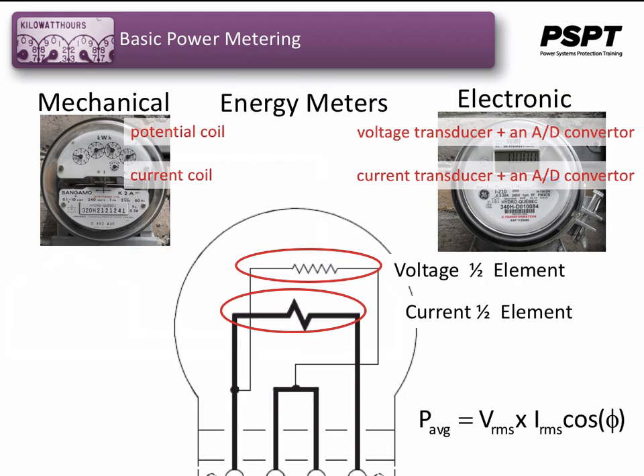Remember from a previous chapter that energy meters, regardless of their makeup, mechanical or electronic, are considered to be made up of meter elements. A potential coil or a voltage transducer and an A to D converter make up a half of the element of the meter, and a current coil or a current transducer plus an A to D converter make up the other half element of the meter. Together they make up a single element of a meter that can be used to measure power and energy consumption by a single phase load.